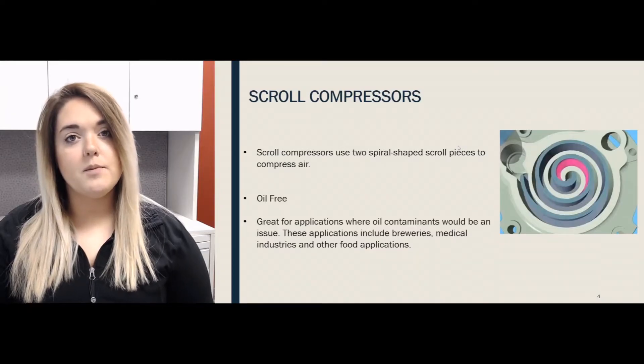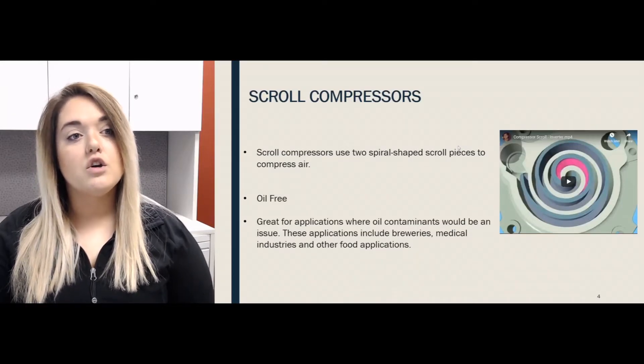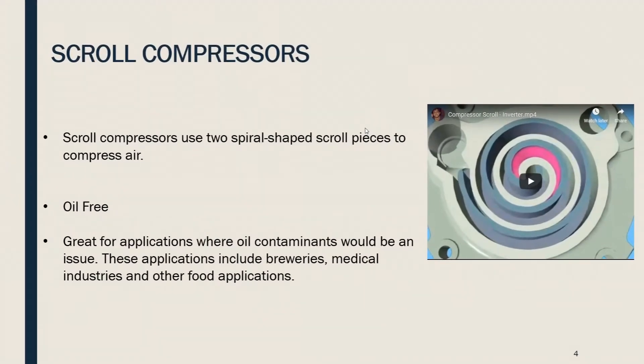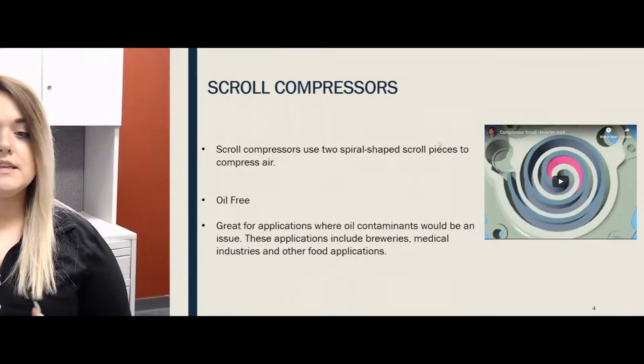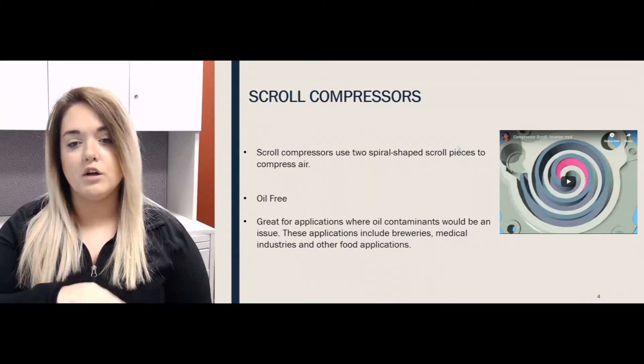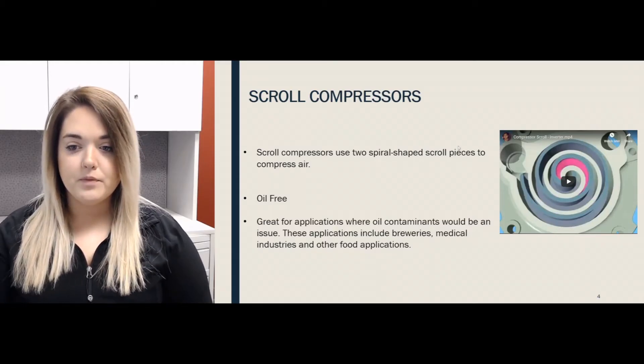The other type of industrial air compressor we carry is the scroll compressor. Scroll compressors compress the air using two spiral-shaped scroll pieces. One scroll is stationary and the other fits inside it and is moved in a tight circular motion, pressing against the inside of the stationary scroll and continuously moving the air along toward the center.